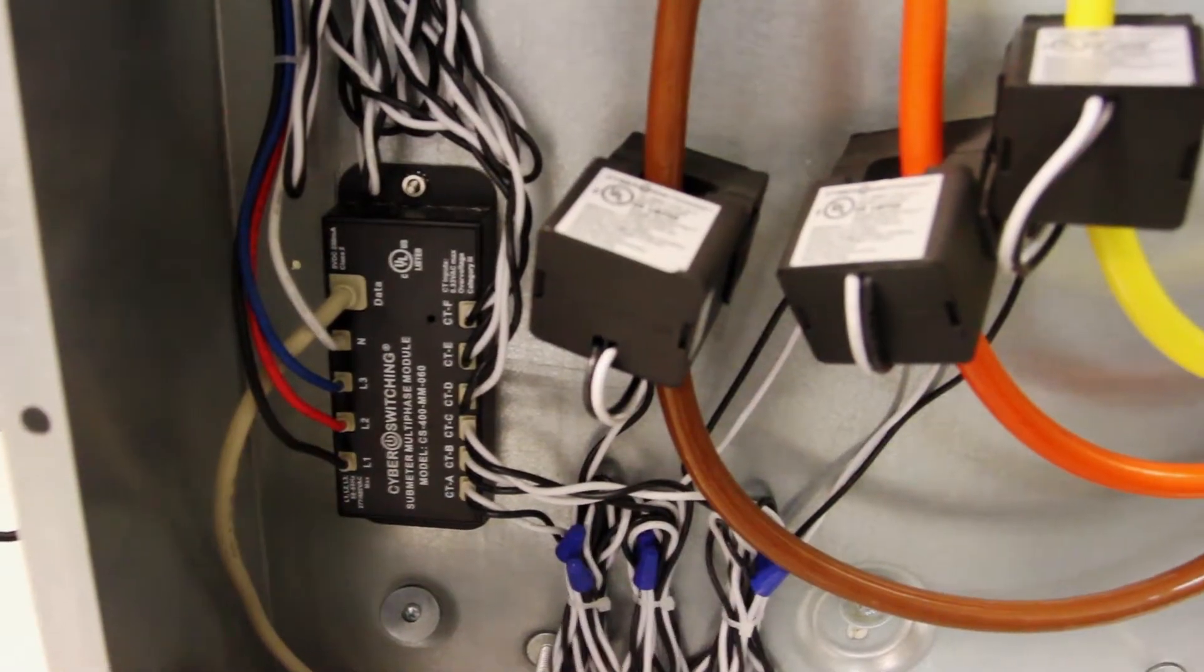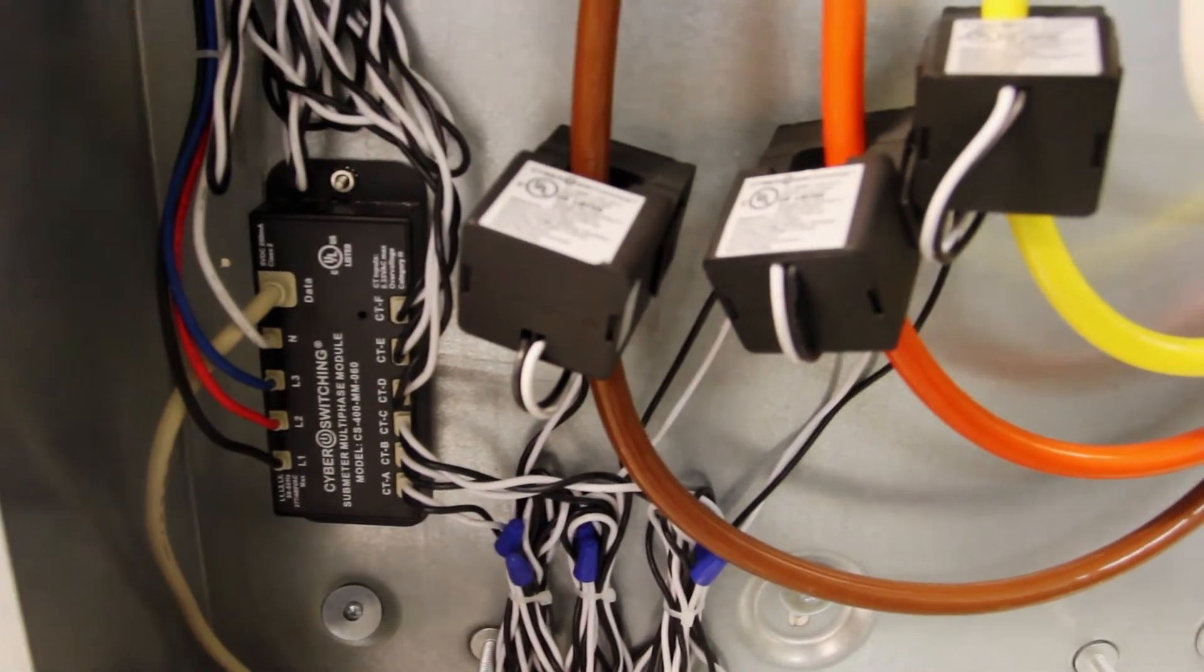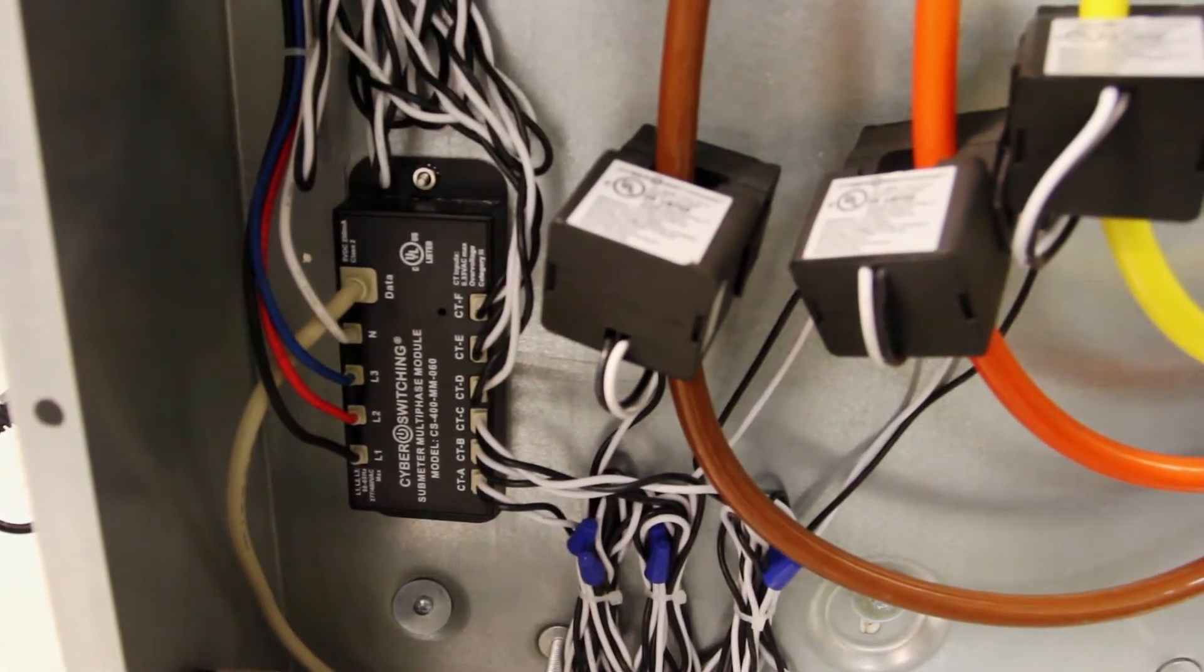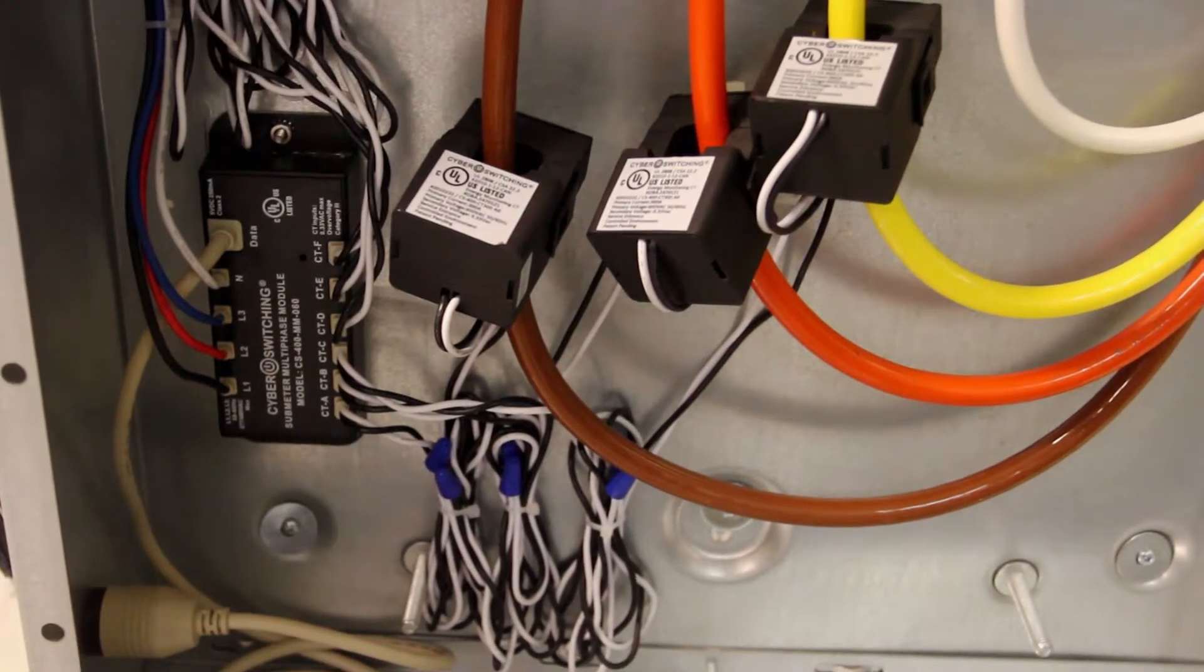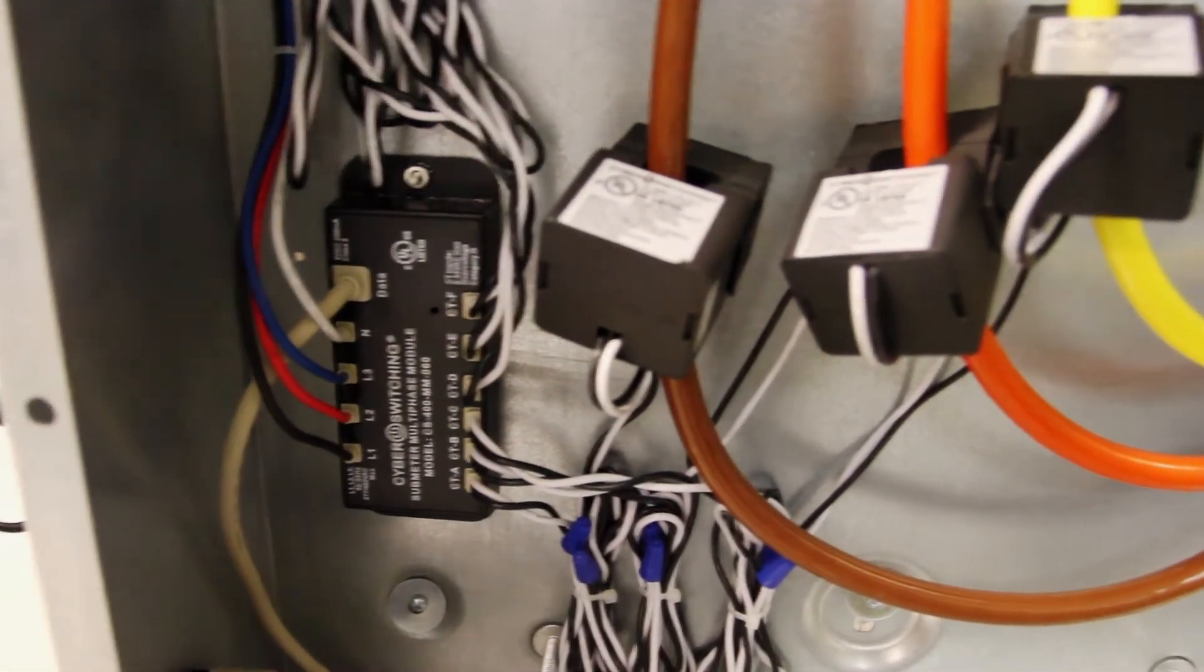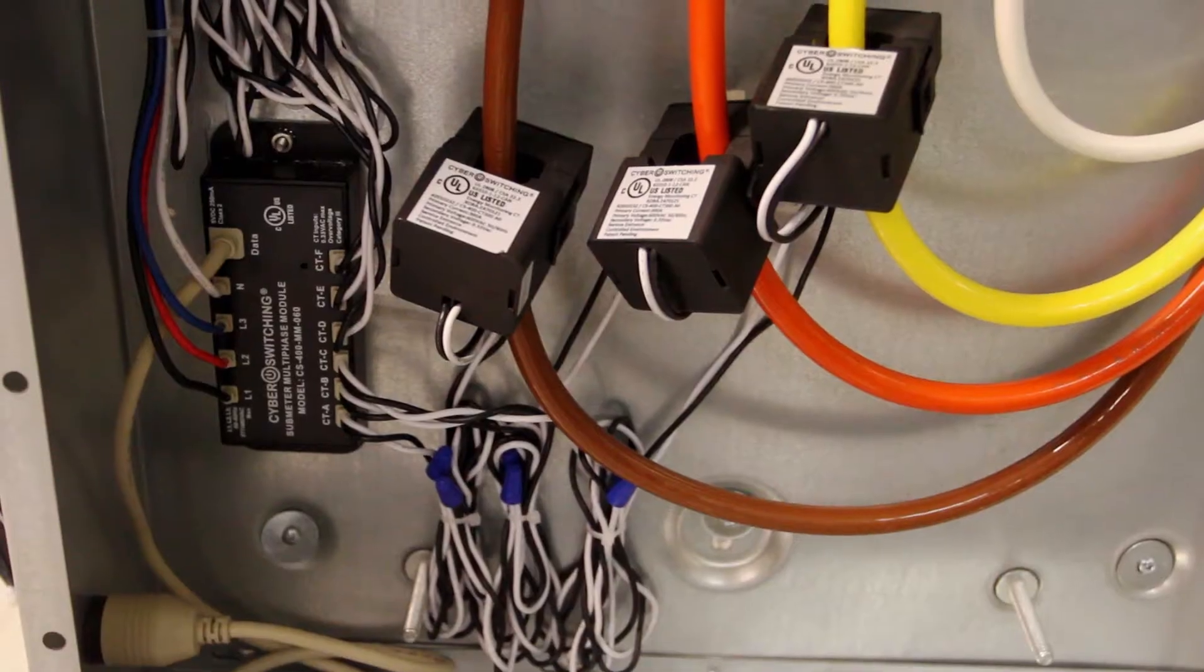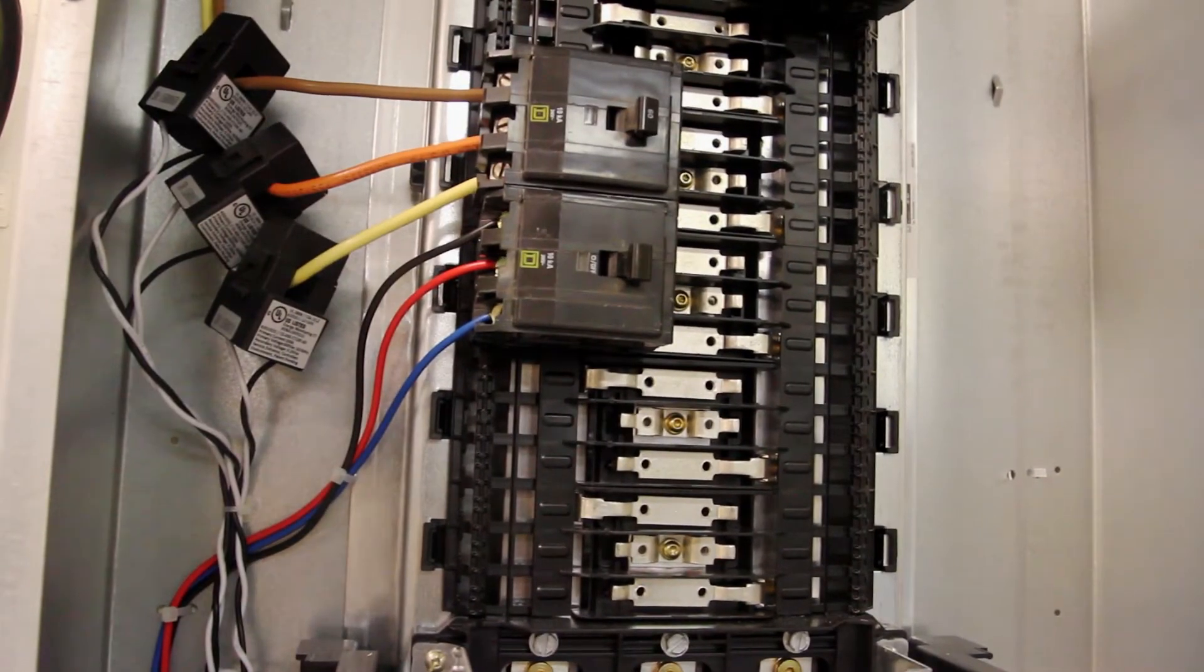Securely mount the module inside the panel and connect lead wires to the installed current transformers. Connect line voltage lead wires to the input breakers for each phase being monitored. In this installation, the module is monitoring load at the service input to the panel and at the individual breaker level.